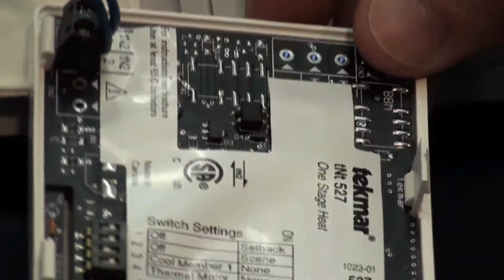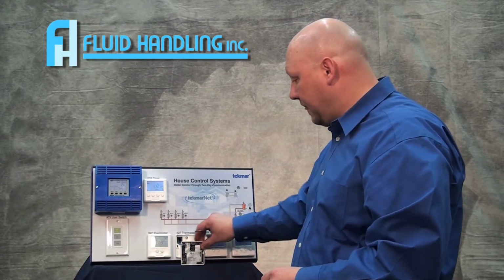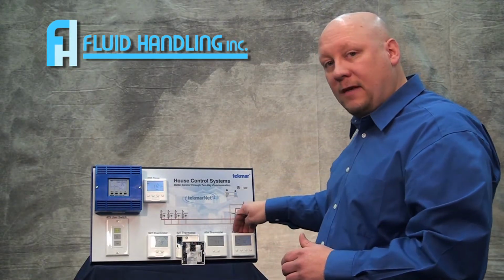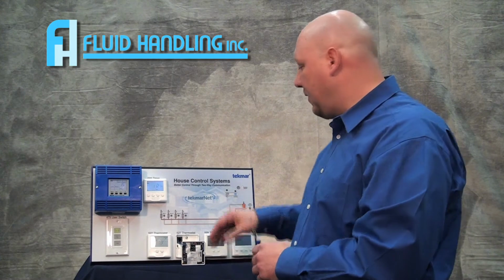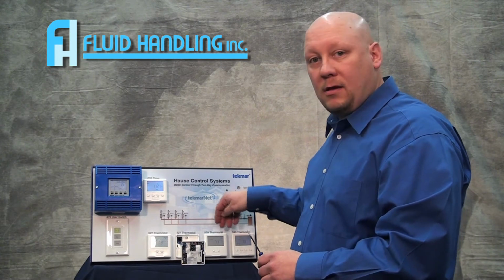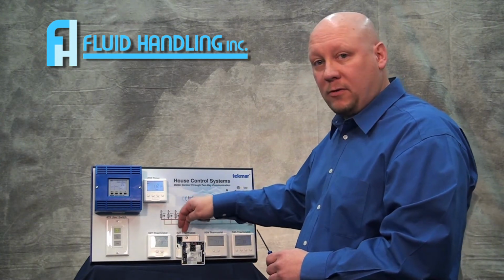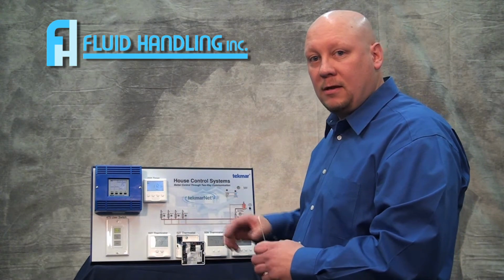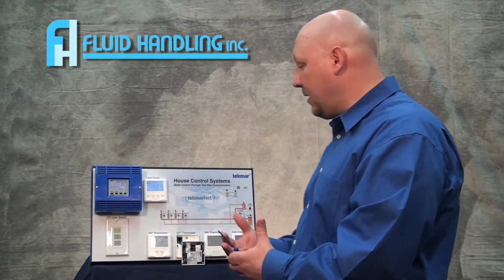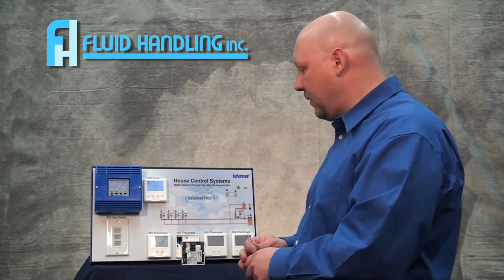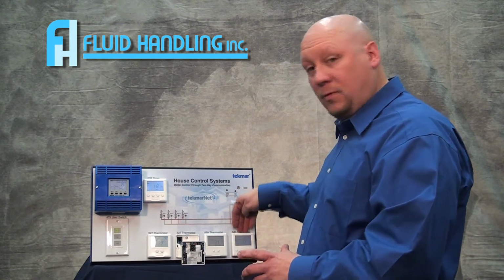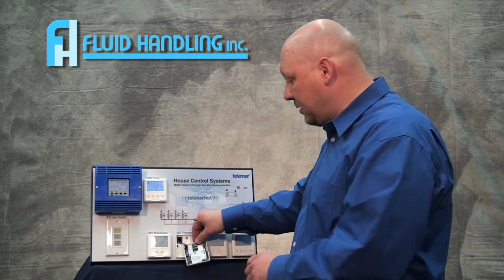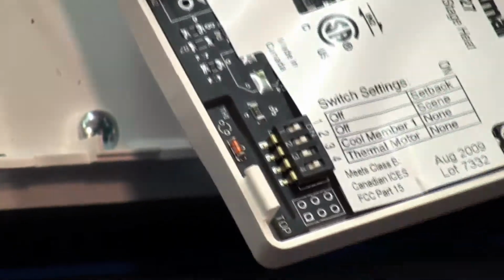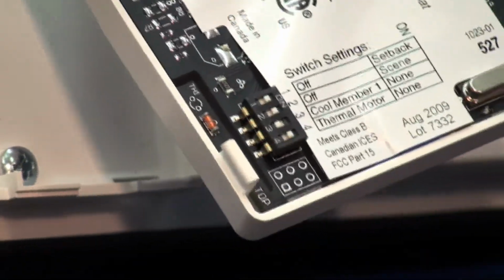If it's a cooling member, with Tekmar, the 530 is a cooling master. It's handling the air conditioning. It can, in the cooling mode, look at the temperature of the 527 and 528 and do an average temperature reading and help even out the cooling within the home. So in this case, we have the 530 as a master, so I'm going to set my cooling member to 1. So it belongs to my cooling master number 1 stat.